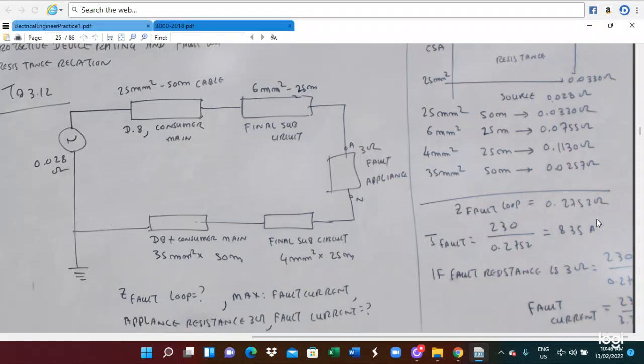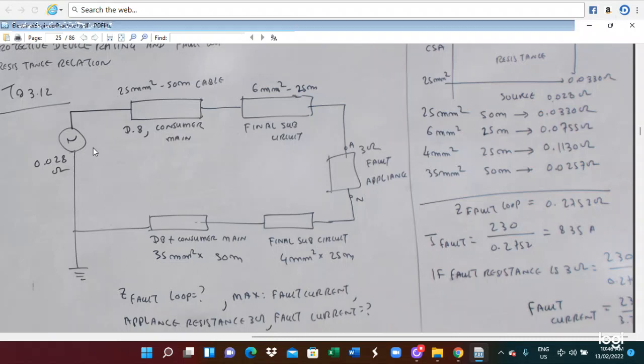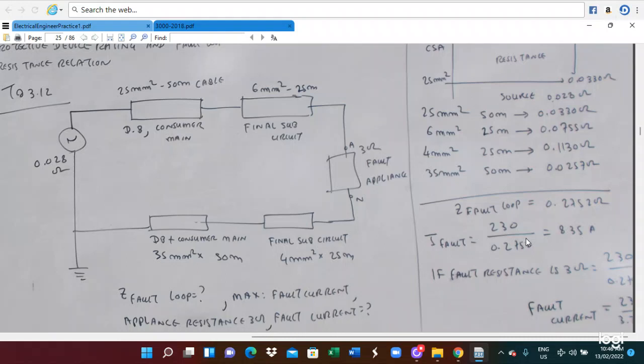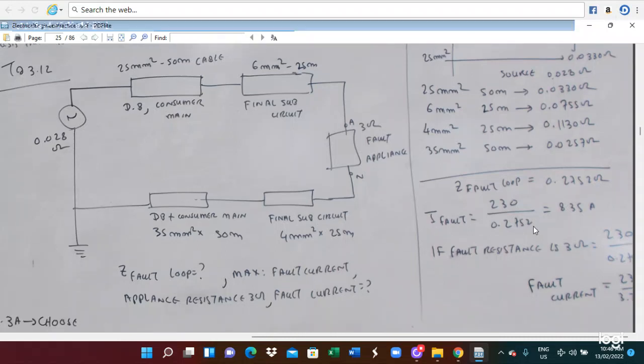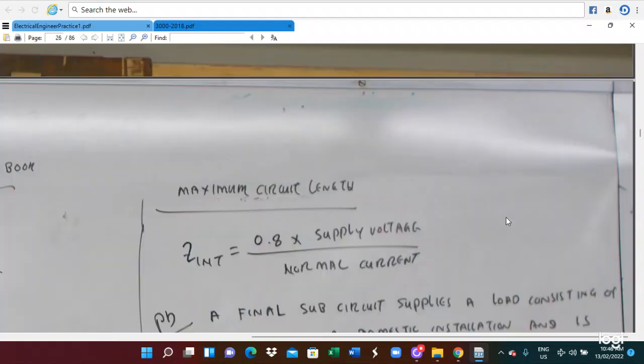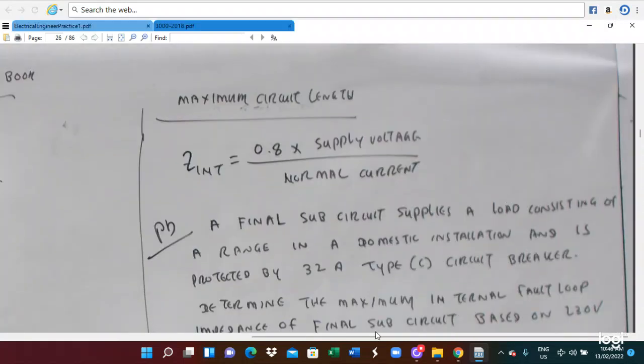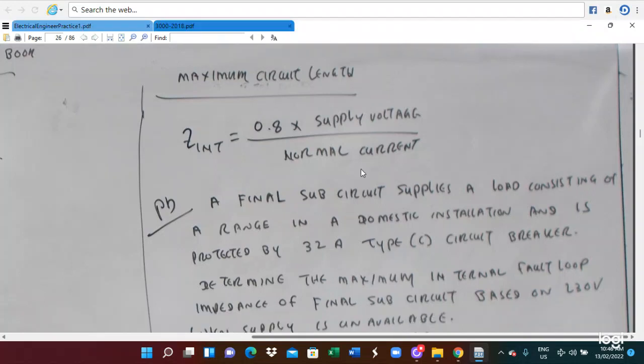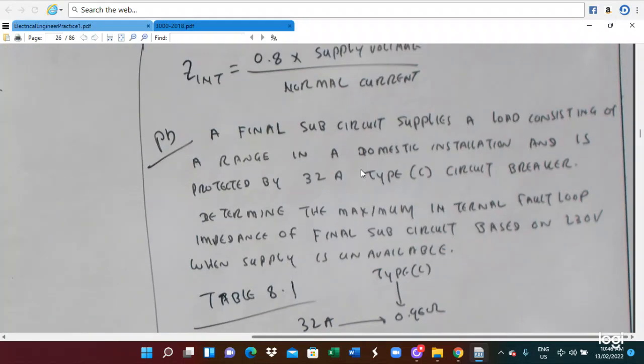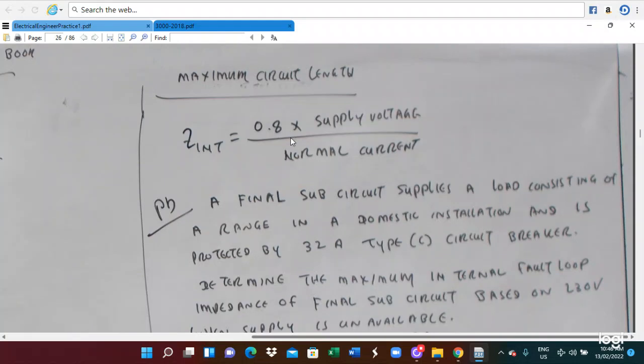After you have the fault loop impedance, with a supply voltage of 230 volt, the supply voltage divided by the fault loop impedance gives the fault current. In this way, you can calculate the fault current. Sometimes you also have to calculate the maximum circuit length, how much circuit length can be utilized. In this case, we have to find the internal impedance Z, using this formula: Z internal impedance is 0.8 multiplied by the supply voltage divided by the normal current. This is the way we calculate the maximum circuit length.